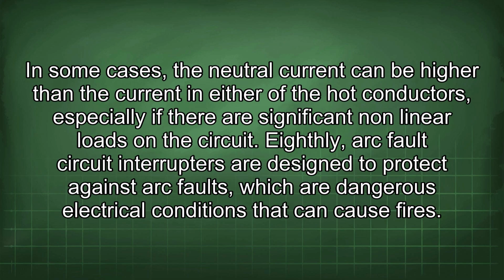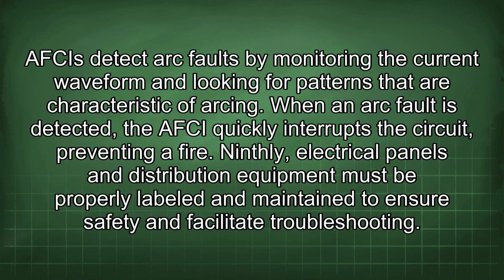In some cases, the neutral current can be higher than the current in either of the hot conductors, especially if there are significant nonlinear loads on the circuit. Eighthly, arc fault circuit interrupters are designed to protect against arc faults, which are dangerous electrical conditions that can cause fires. AFCIs detect arc faults by monitoring the current waveform and looking for patterns that are characteristic of arcing. When an arc fault is detected, the AFCI quickly interrupts the circuit, preventing a fire.